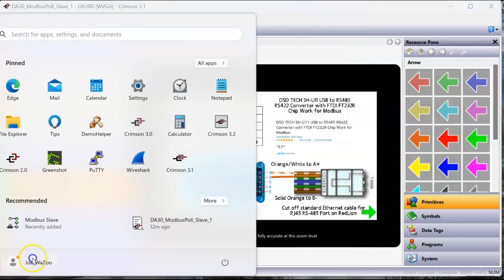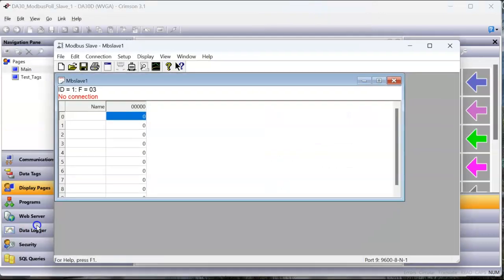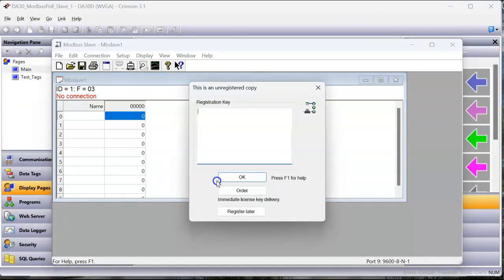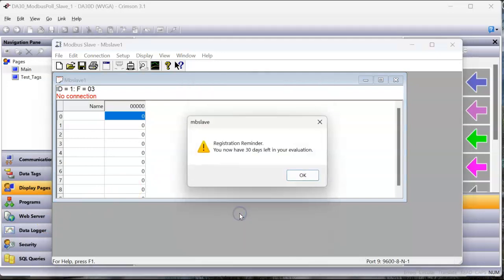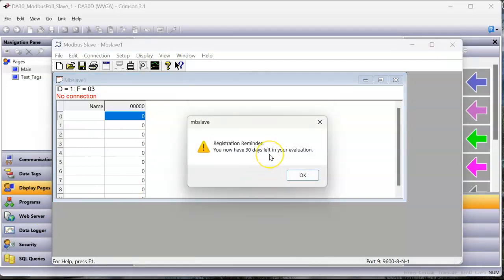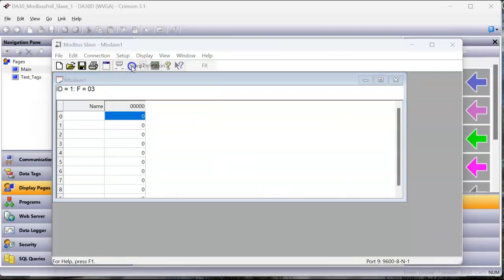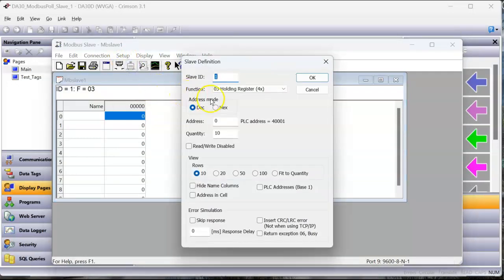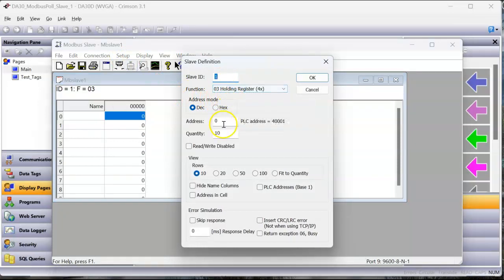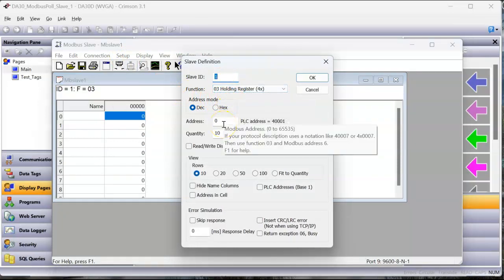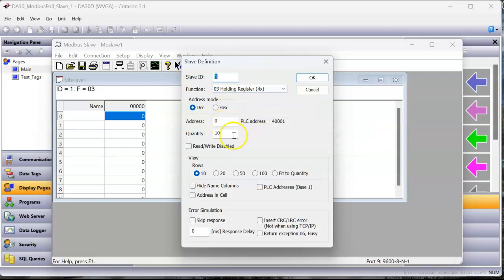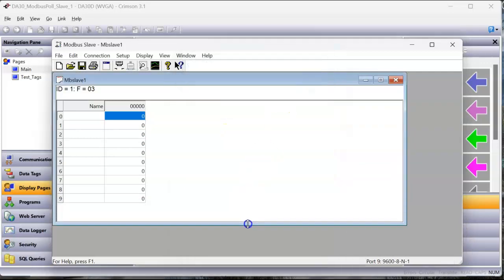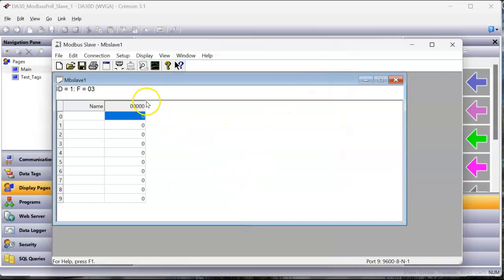And then I'm going to fire up Modbus Poll here. So here's Modbus Poll. Comes up here, registered later. You get 30 days. I think it's 100 bucks for this program or something, but for this case, I'll try it out. I'm going to setup, slave definition, slave number one. I'm going to be holding registers. Starts at zero. That's actually 40,001. And I'll set it up for 10 registers. That's perfect. Make this a little bigger so you can see all 10.